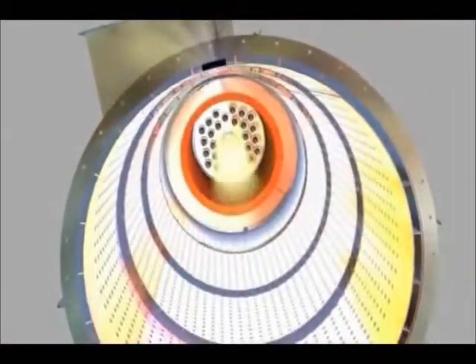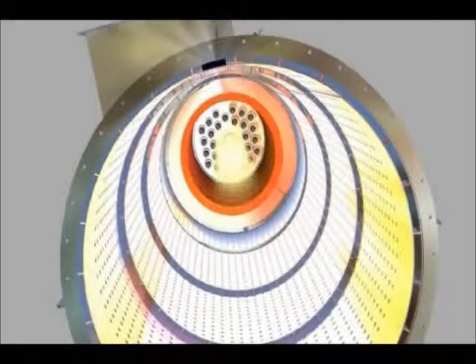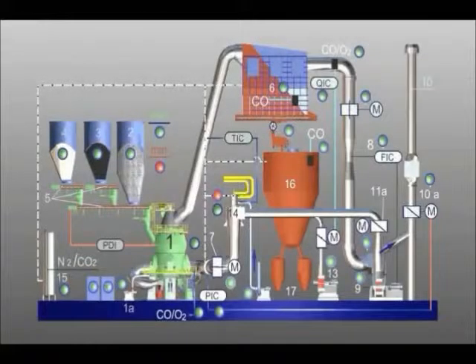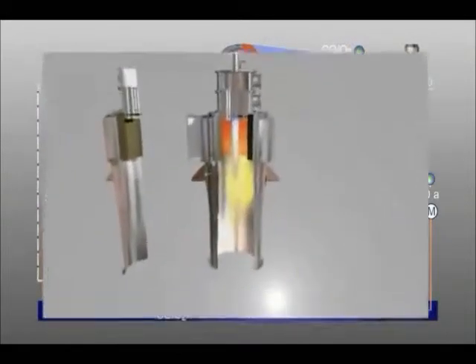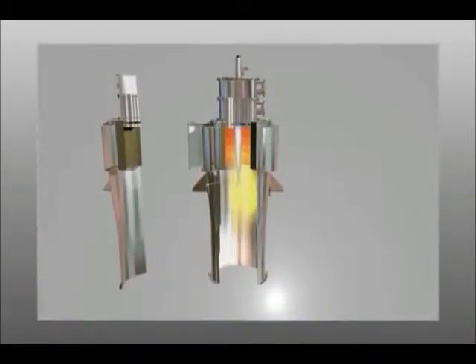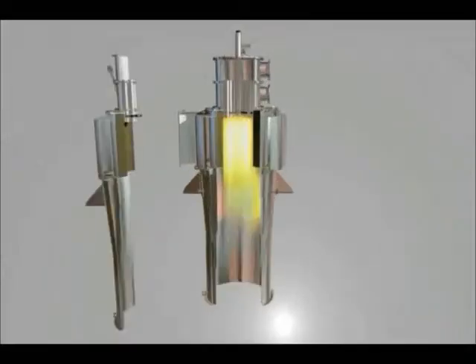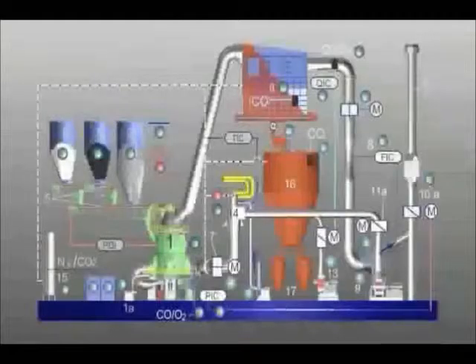The start burner fulfills various functions. It serves to warm up the combustion chamber muffles to temperatures of over 350 degrees Celsius and the entire plant to temperatures higher than 65 degrees Celsius. When these two preconditions are met, the main burner is enabled. At the same time, the volume flow of process gas is set to 70 percent of the maximum value.